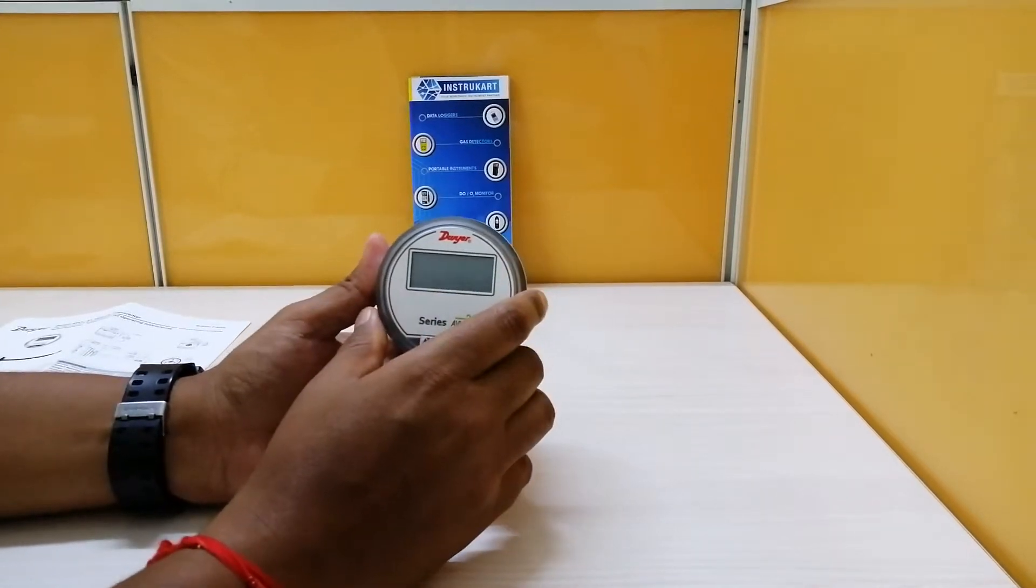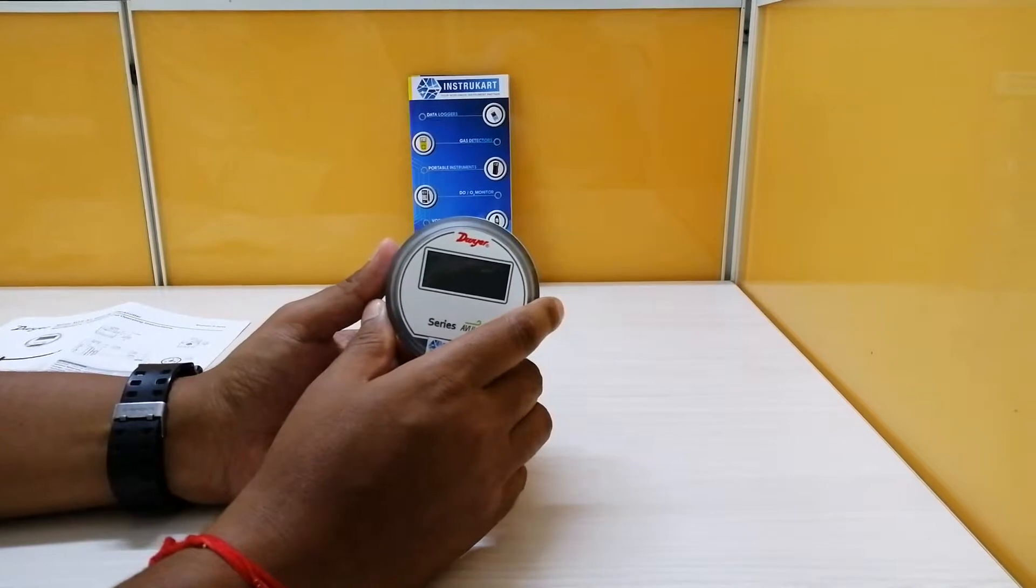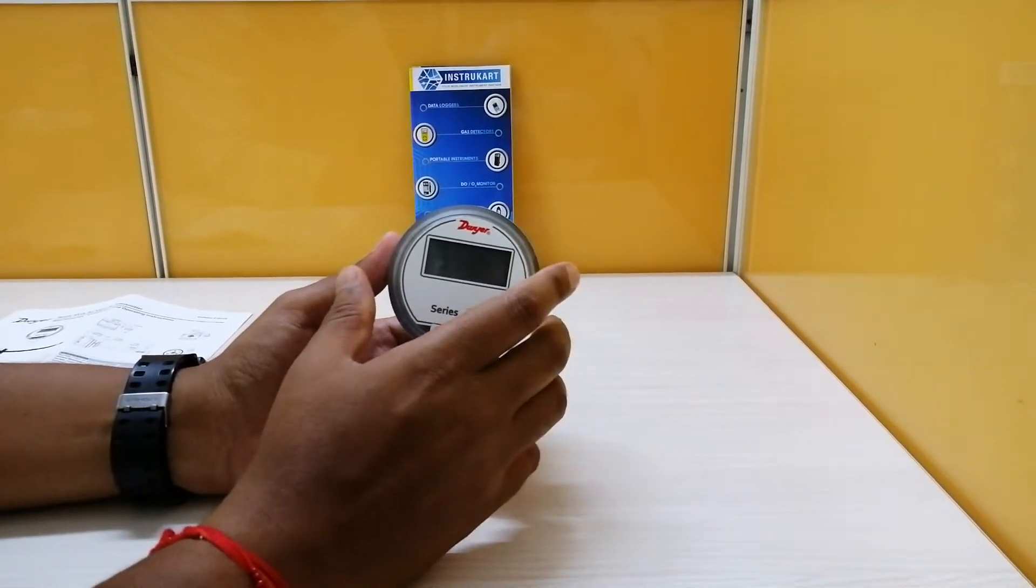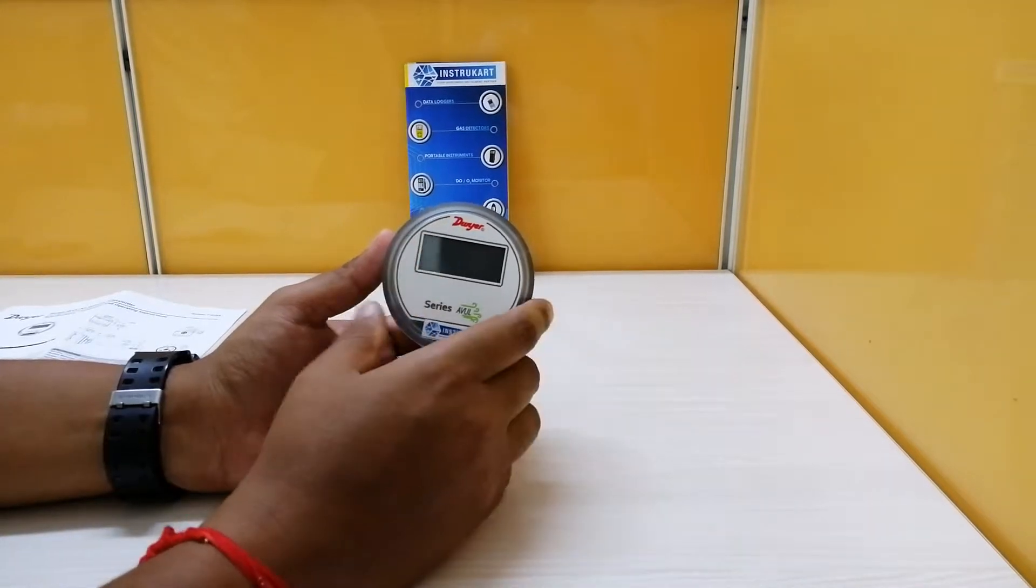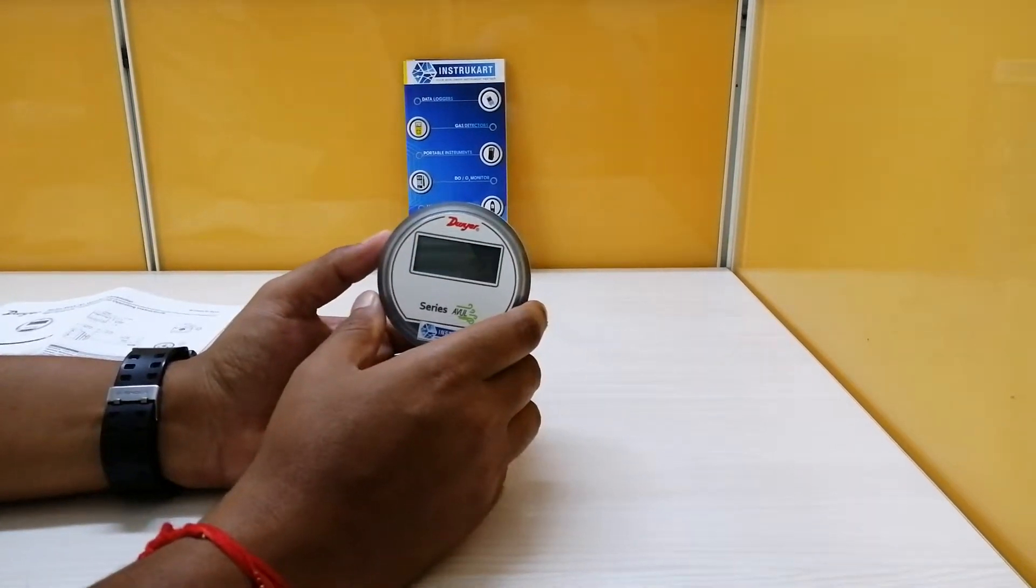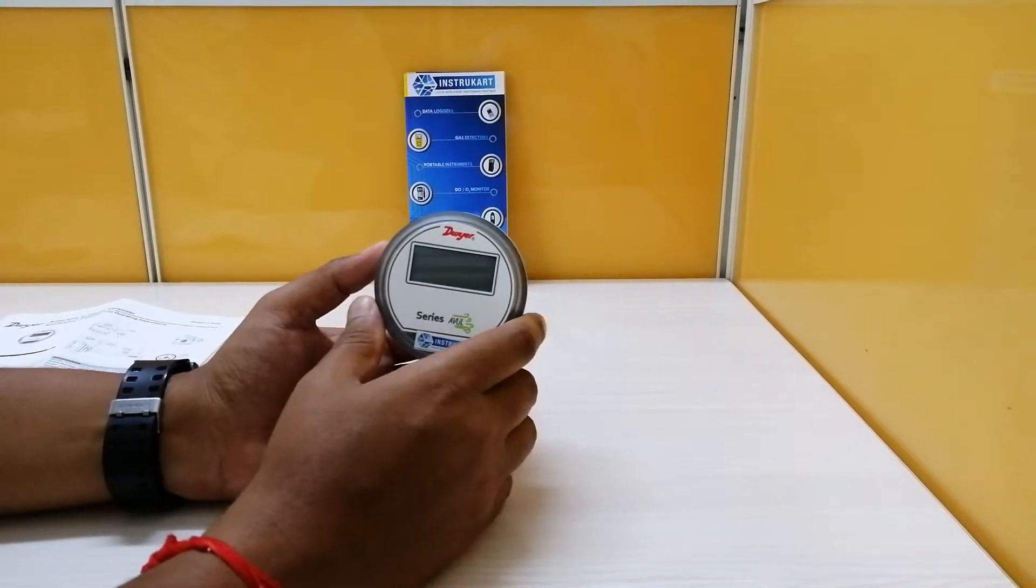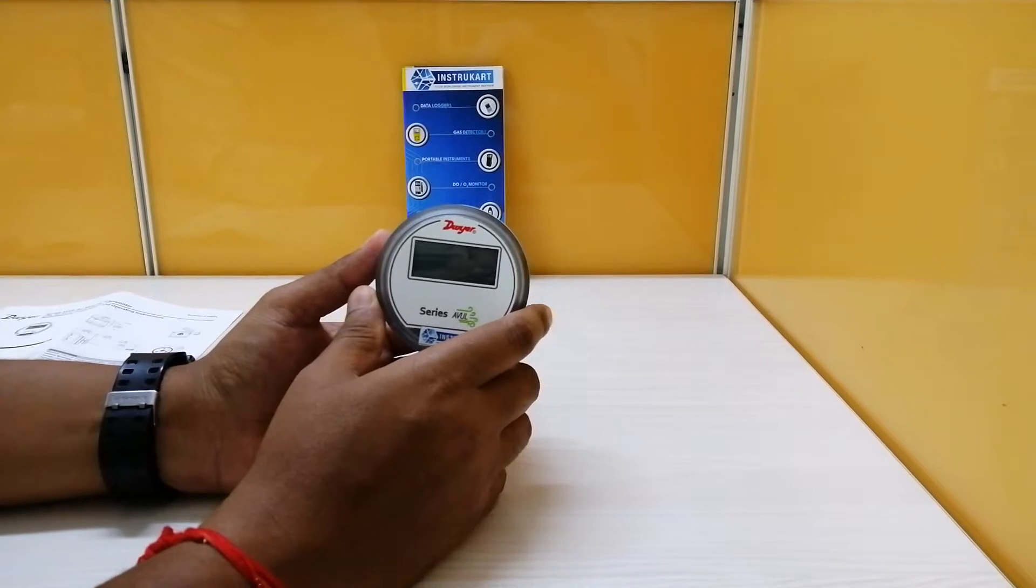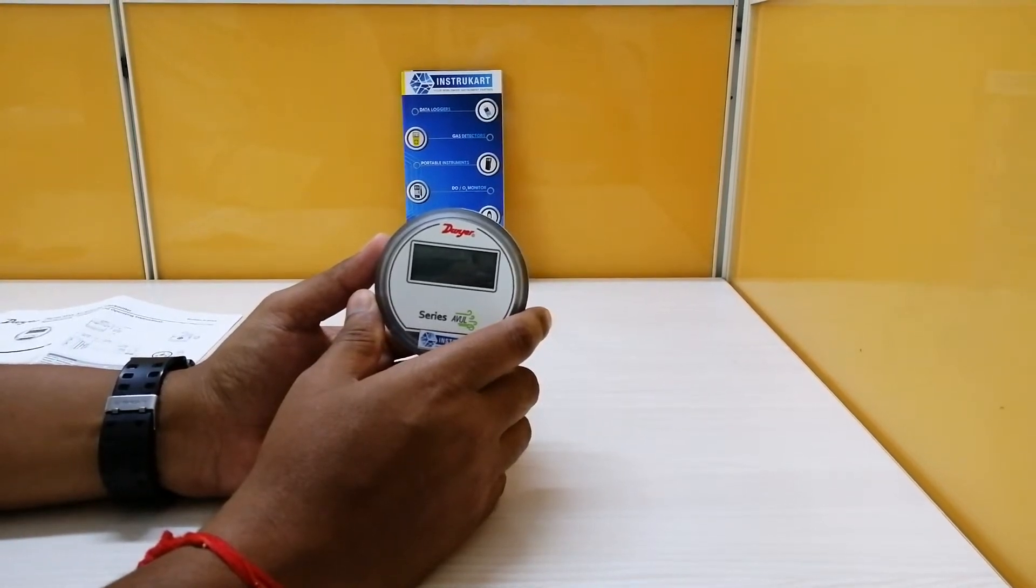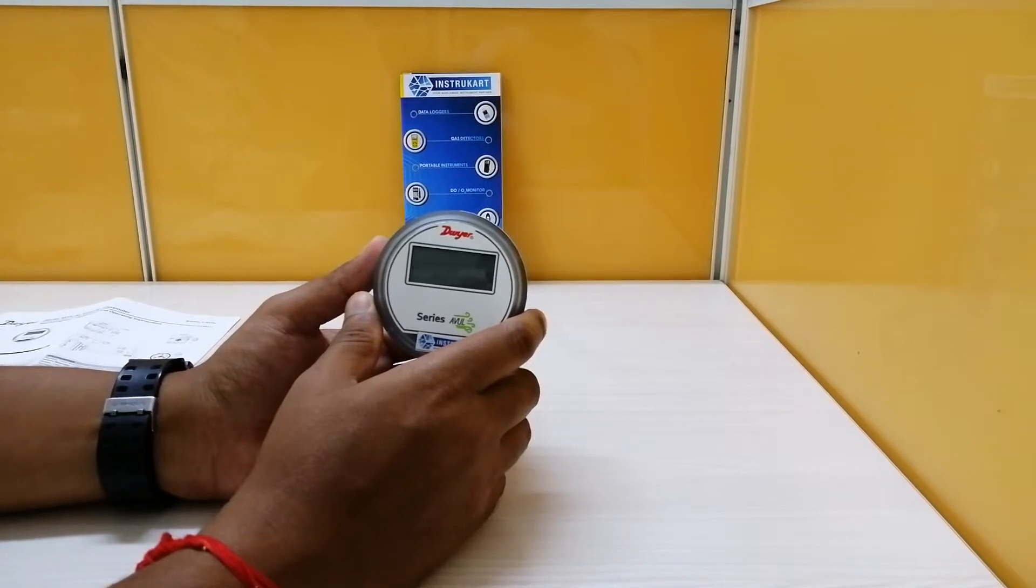This air velocity transmitter has a range of 0.0 to 5, 0 to 10, 0 to 15, or 0 to 20 meters per second, which can also be read as FPM. It has an accuracy of plus or minus 5% of reading or 0.2 meters per second.